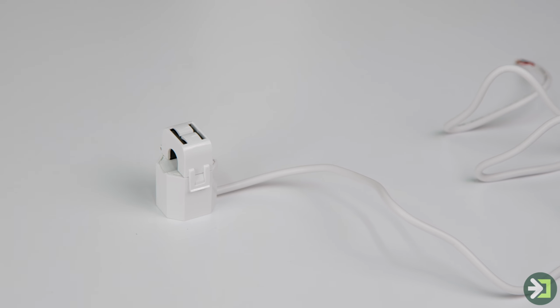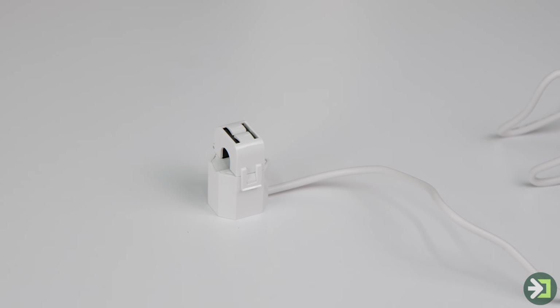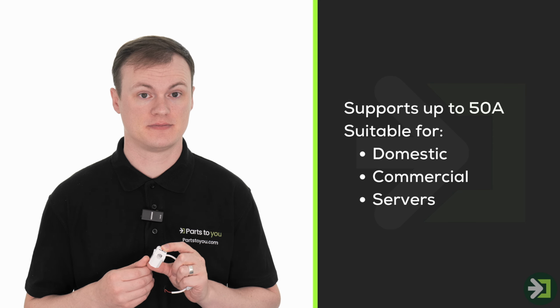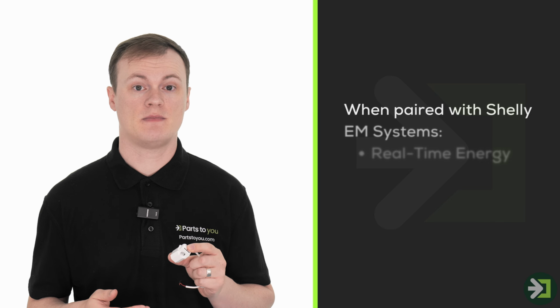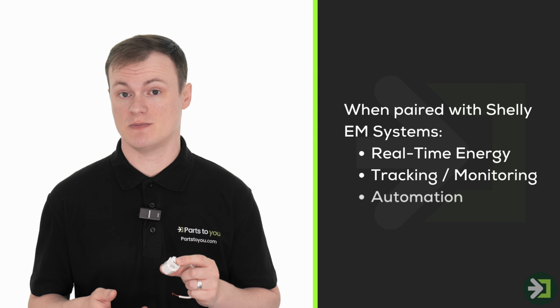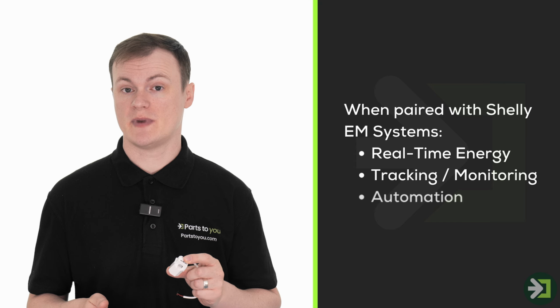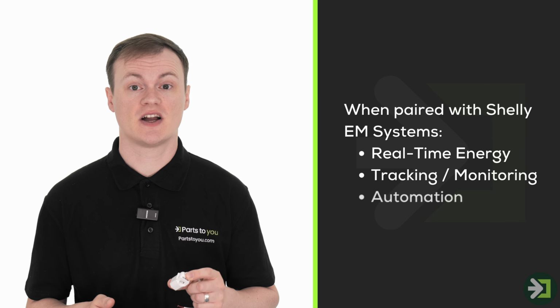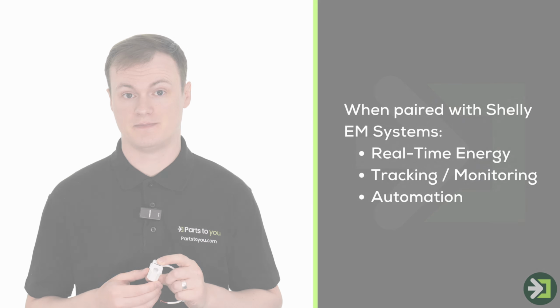And because this is a split-core current transformer, installation is dramatically easier in retrofit environments where disconnecting wiring may be impractical, inconvenient, or something you'd rather avoid entirely. The clamp supports current measurements up to 50 amps, making it suitable for most household circuits and many small commercial applications. Pair it with a compatible Shelly EM and you gain access to real-time energy monitoring, usage tracking, automation triggers, and detailed consumption insights through the wider Shelly ecosystem.